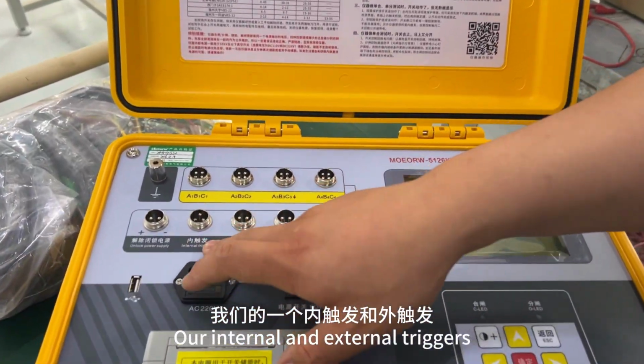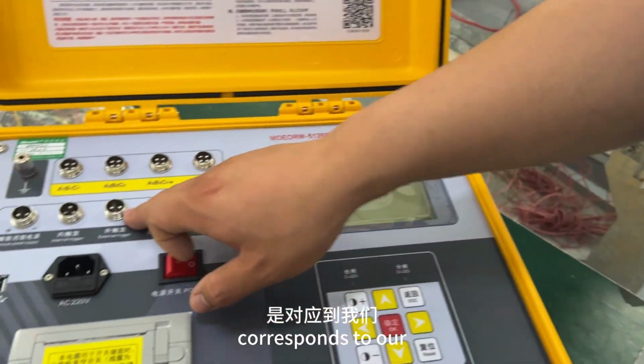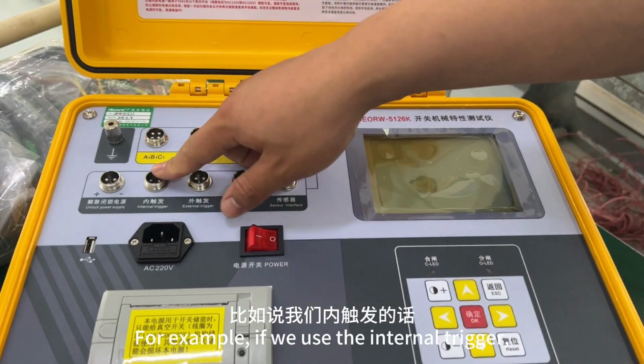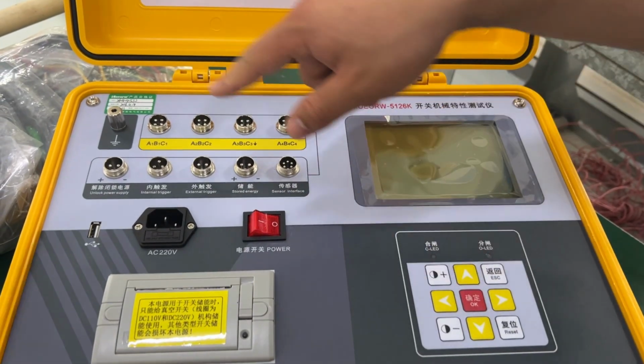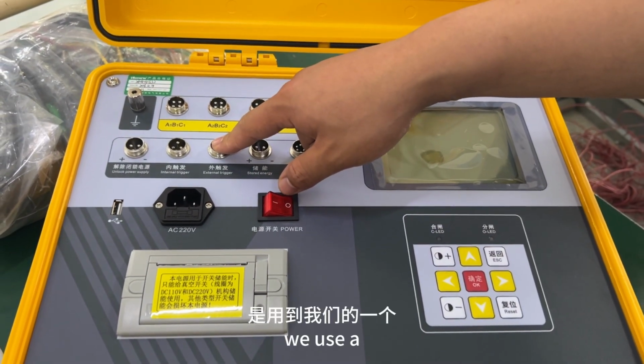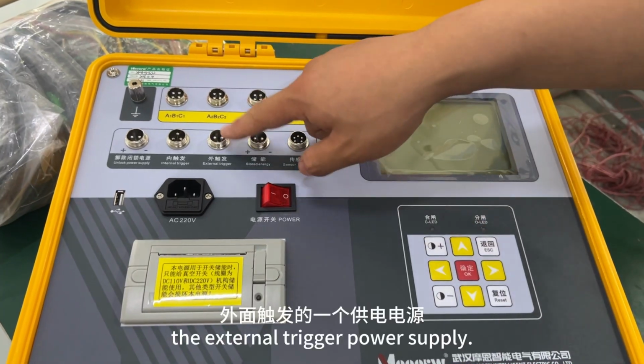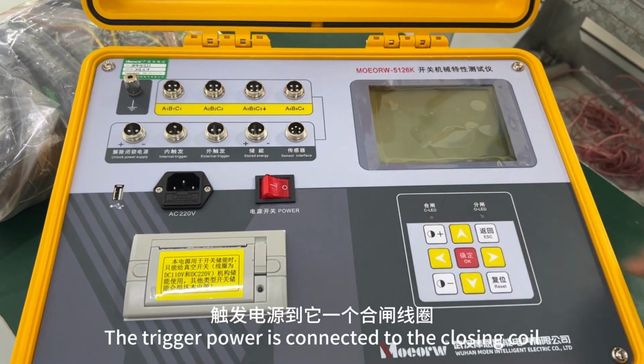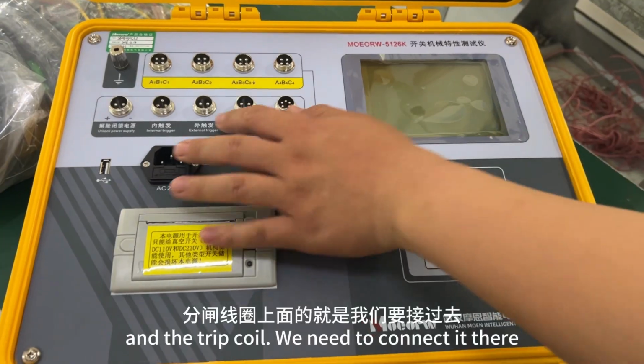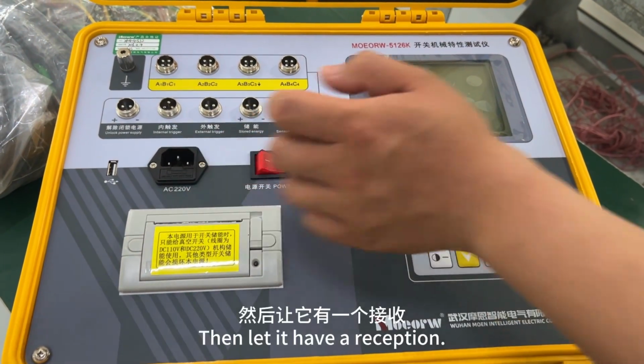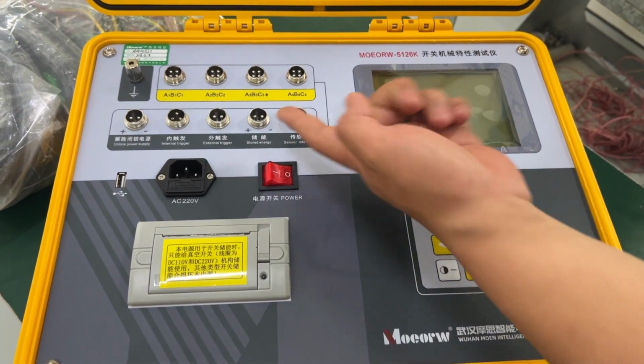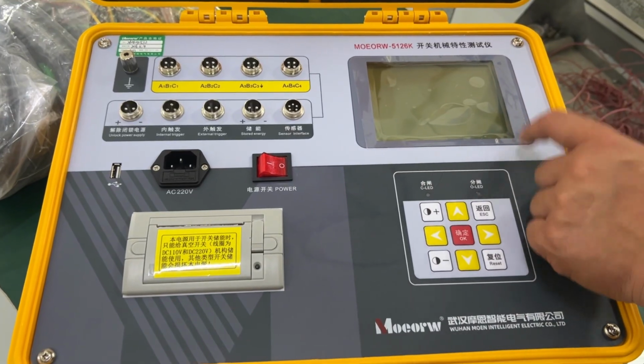Our internal and external triggers correspond to our settings. For example, if we use the internal trigger, we use our own instrument to trigger it. For the external trigger, we use the external trigger power supply. The trigger power is connected to the closing coil and the trip coil, and we need to connect it there. Then let it have a reception, so that we can synchronize and test it.